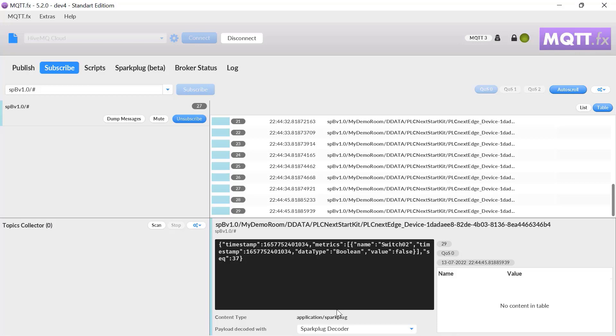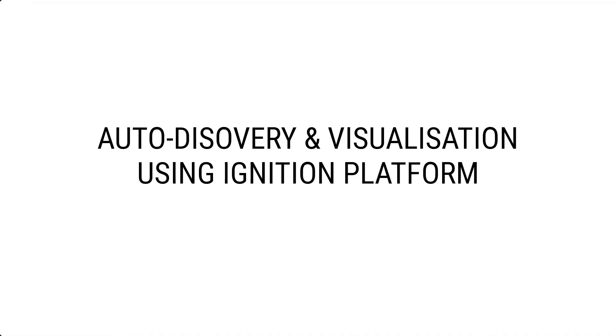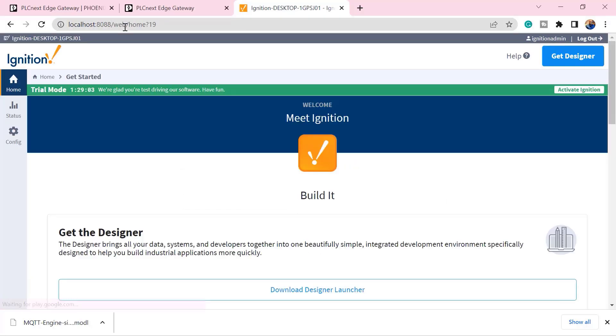Now let's set up our Ignition platform to connect to our HiveMQ Cloud broker, receive these Sparkplug messages, and visualize them. I'll open my Ignition Scada platform running on my PC. Here I need to configure an MQTT module from Cirrus Link called MQTT Engine — by simply putting in my HiveMQ Cloud broker details, the MQTT Engine module will connect to the broker and automatically discover data being published by my PLCnext Edge Gateway.